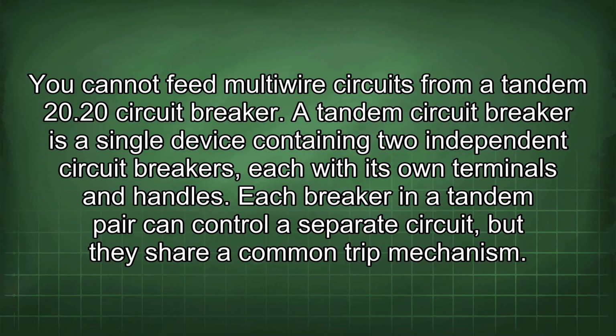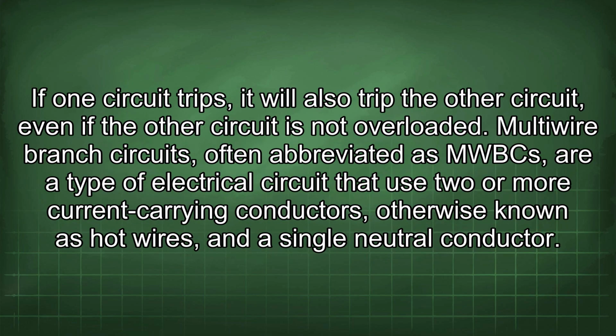You cannot feed multi-wire circuits from a tandem 20/20 circuit breaker. A tandem circuit breaker is a single device containing two independent circuit breakers, each with its own terminals and handles. Each breaker in a tandem pair can control a separate circuit, but they share a common trip mechanism. If one circuit trips, it will also trip the other circuit, even if the other circuit is not overloaded.